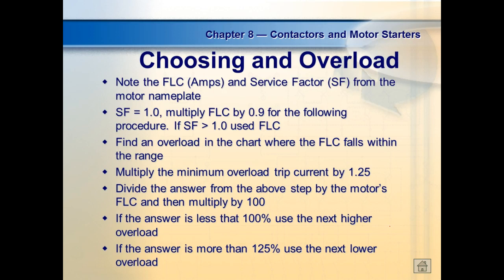So the heaters are already sized to allow an overload, not an overload heat, but over what is horsepower rated. If they're sized to allow a service factor greater than one, that means if I've got a motor with a service factor of one, I'm going to have to degrade the amount of current it could actually pull. Does that make sense? If I've got a service factor of one, I'm only going to use 90% of current, so I multiply by 0.9. Not the service factor, the full load current.